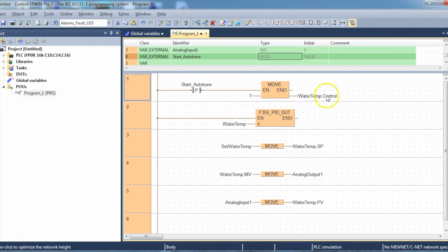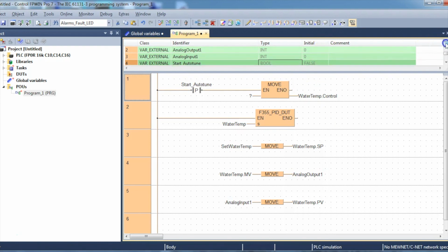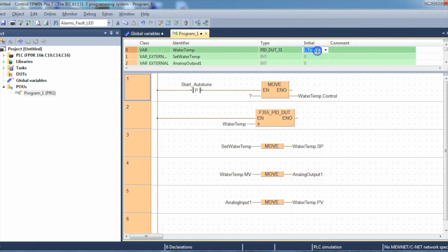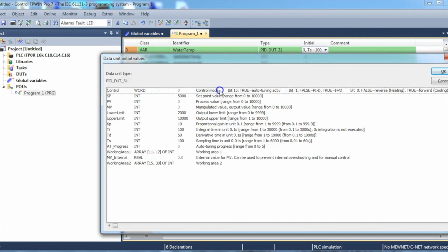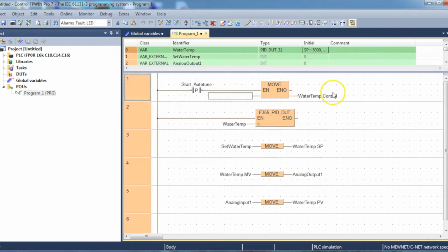So now what we do to move that in, if you remember when we looked at the initial value up here in this function block, it says here control mode bit 15 true equals auto tune active. So we need to put a number in here in hex because it is a word value. So the hex value that will make a 1 appear in your bit 15 is 8000.